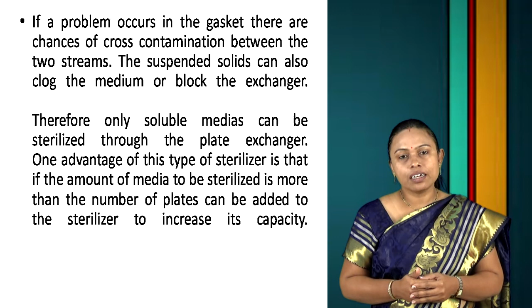The indirect plate heat exchangers, in this type of sterilizers, have a design containing plates through which the streams are circulated in opposite direction. The plates are separated by gaskets. If a problem occurs in the gasket, there are chances of cross contamination between the two streams. The suspended solids can also clog the medium or block the exchanger. Therefore, only soluble media can be sterilized through the plate exchanger type. One advantage of this type of sterilizer is that if the amount of media to be sterilized is more, the number of plates can be added to the sterilizer to increase its capacity.